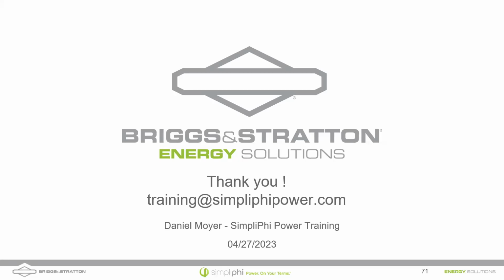And if you do 100% depth of discharge every single cycle, we only expect you to get around 3,000 cycles, or about 10 years out of the battery. We realize people will use a combination of these, but that gives you a good idea. These are some of the best numbers in the industry — we use premium battery cells, top of the line BMS systems made in the US and designed in California, so we expect really good comparable lifetimes out of these batteries.